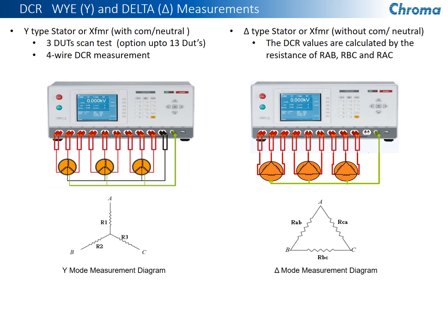Chroma's put together an algorithm internal to our firmware on this unit that allows it to detect or to differentiate and calculate the actual resistance of the winding of each individual winding. We also have that same ability to do it for a delta configuration like you see on the right. And with that, you would see that the windings wouldn't be in series, but they would actually be 2 windings in series, but that are actually paralleled across the winding under test, and that would definitely cause a lower resistance reading. So again, we can do a calculated value of the actual resistance of each individual winding to give you a proper measurement of that winding.